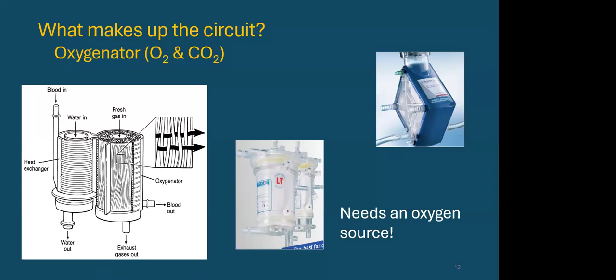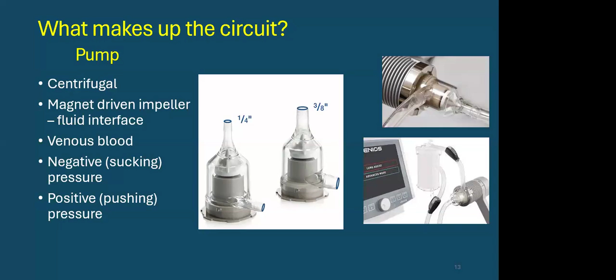The pump, there are different configurations of pumps. We're looking here at the one we used on the Fresenius device or the Xenios machine. This is a centrifugal pump. There are two sizes for the smaller and then the larger patients. The base of the pump is a magnet, and it floats an impeller above it. So there is no contact between the part of the pump that actually spins and the magnet below it. At the top, you have the venous blood entering, and below is where the blood exits towards the oxygenator. It exerts a negative pressure at the top and then a positive pushing pressure at the bottom.